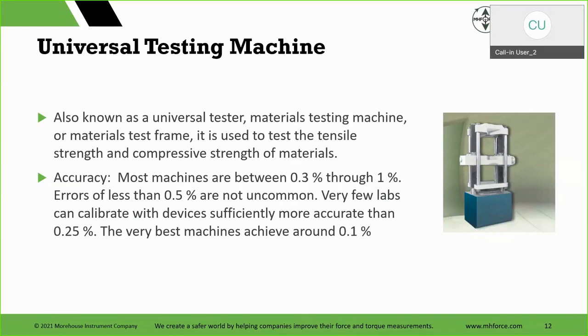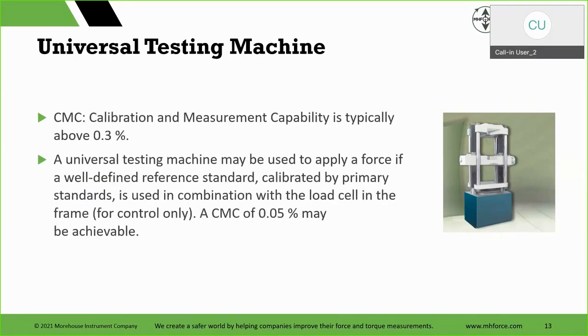The very best machines, like a Tinius Olsen Super L, can achieve about that 0.1%. Still not good. If that's your best starting point, typically that's still not good enough for what your customers are expecting, especially if they want your uncertainties to be a lot better. And we start talking about risk and conformity assessment, all that good stuff. Those numbers do not relate well to what most expectations we've seen, even on those button load cells and whatnot that are out there. So I just wanted to say people use them.